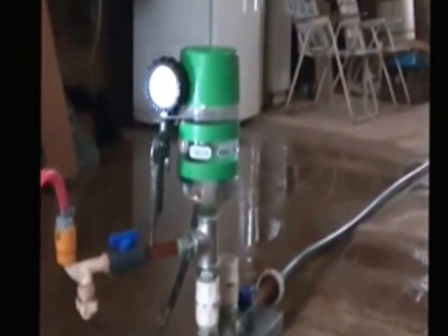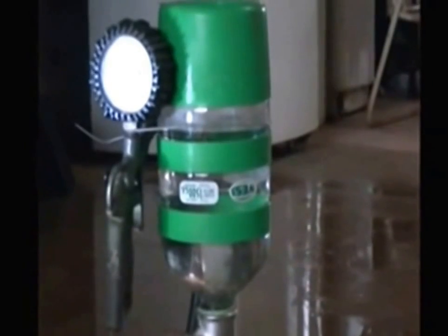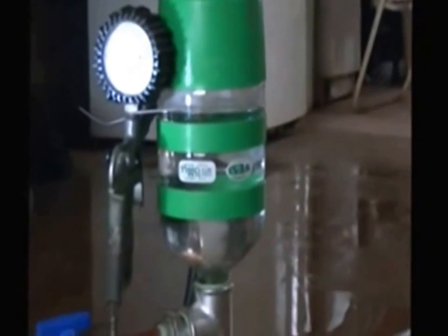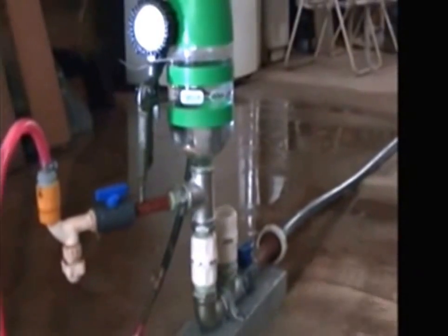There will come a moment when the manometer will stabilize, meaning the maximum supply height. We're already at 18 meters in height. We can lift water 18 meters in height.